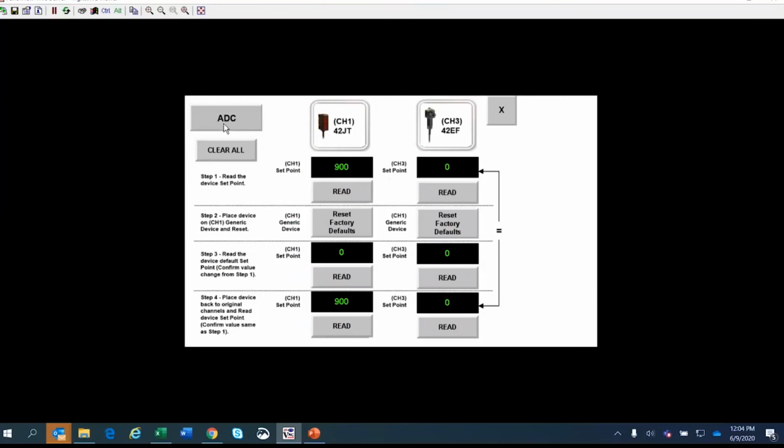When the new sensor is brought in, you remove this sensor, you install the new sensor, and right away, instantaneously, it's going to take on 3 inches as a sensing range. Whatever was the setup, the 900 setup is stored in the PLC. It gets downloaded automatically, instantaneously into the sensor. At the same time, it downloads whether it's a light operate or dark operate, whether the push button on the sensor was locked or unlocked.